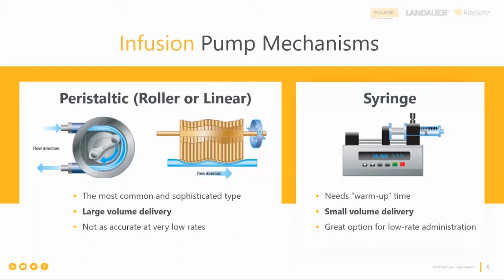So syringe pumps, on the other hand, use an electric driver that slowly depresses the syringe plunger. You can see it in the picture. There's a little syringe on top. So the plunger, when it's moved, pushes the fluid into the patient's vein. Those mechanisms are great for low volume fluid delivery because they can infuse very small doses over a long period of time. However, I would like to make a note also that operators need to be very careful when they use syringe pumps, as they may have a sort of mechanical slack that will not allow for a steady flow rate from the get-go. They will need priming.